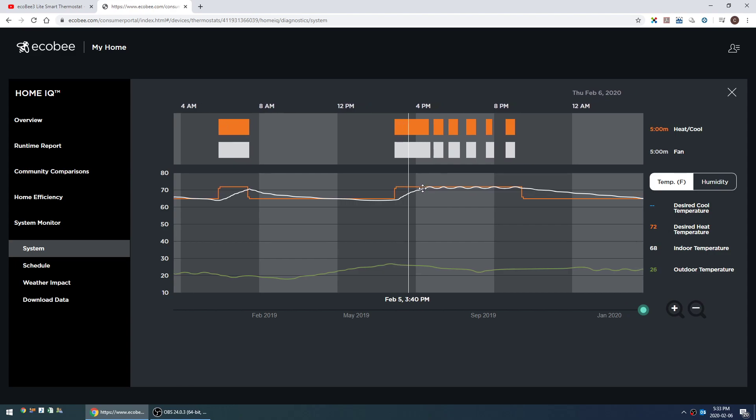Because I allow for a one degree threshold, my furnace is cycling on a little bit less frequently than if I only allowed the default half a degree. But because I allow a degree of variation, these ups and downs are a little bit steeper than they would otherwise be.